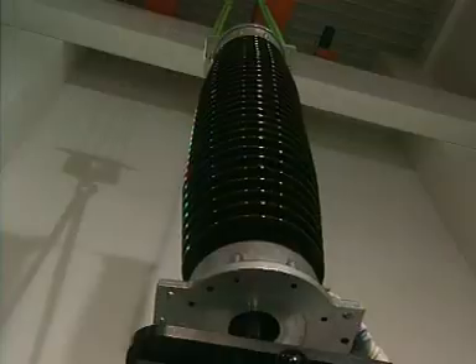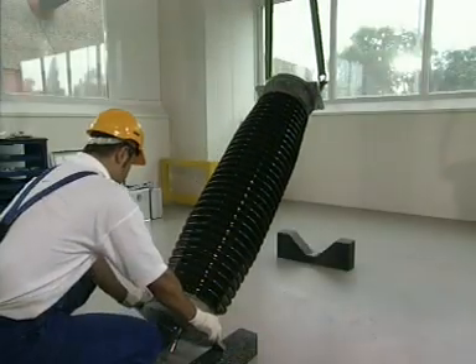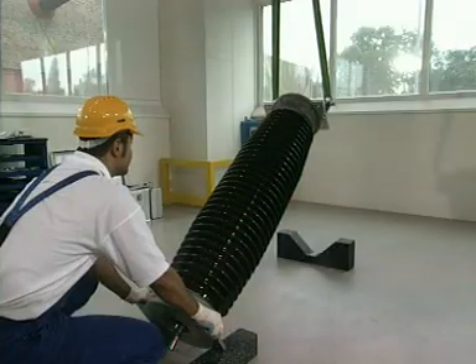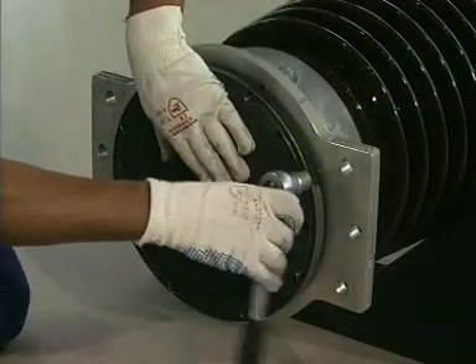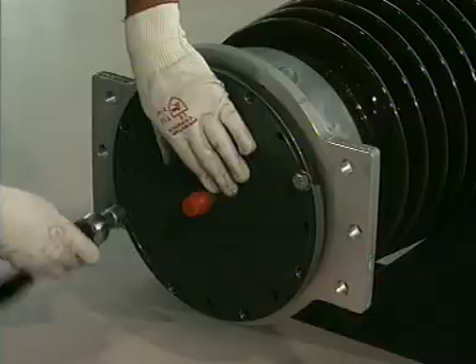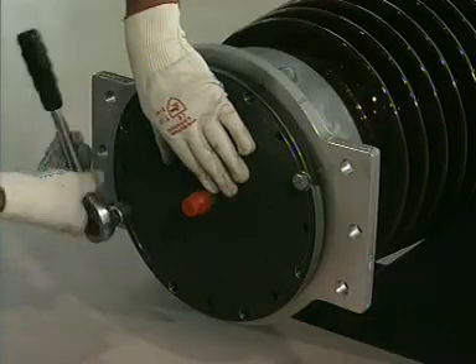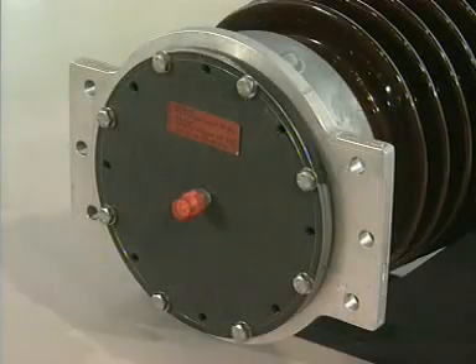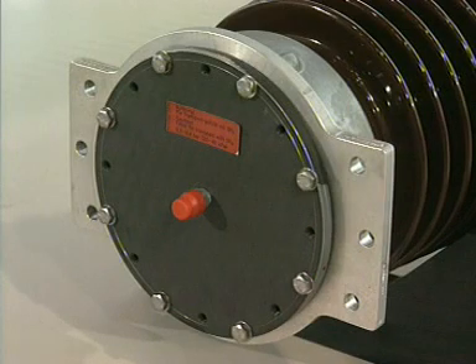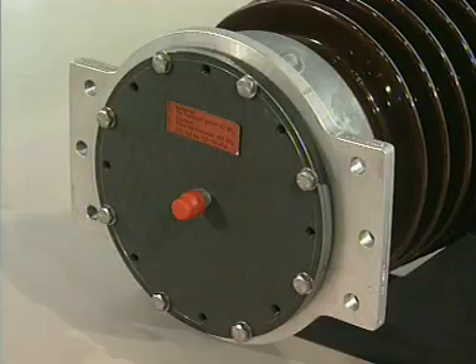Release the interrupter chamber from the mounting device, lift it off and set it down on a suitable surface. Finally, close the interrupter chamber with cover and gasket. Evacuate the interrupter chamber for storage purposes and fill it with nitrogen or new SF6 gas to a pressure slightly above atmospheric.